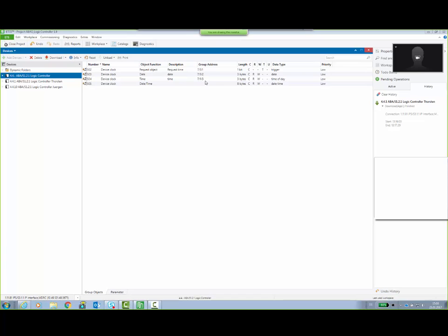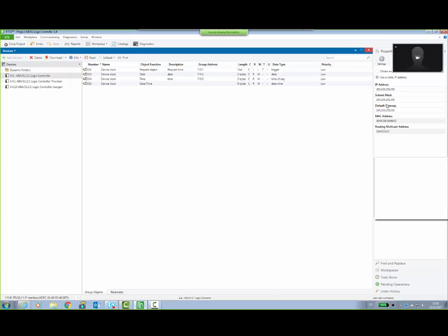One further topic, IP. It's an IP device, so we have to have an IP address inside this component. There are two options. You can obtain an IP address automatically, if you have a DHCP server in your network, as we have right now in our ABB network. Or if you would like to have a static, fixed IP address, you have to click here and assign a fixed IP address here. That's a further option. But this is all in principle.